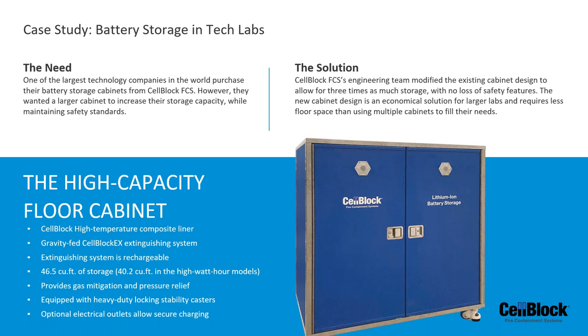Now there is a little downside space-wise associated with doing that. If you increase to the high watt hour shelf, we have to put in more fire suppression mineral, which means if the shelf had 12 inches of clearance, now it may only have 10 inches of clearance or head height of freeboard, because we just have to put more material in. But that's the rundown on the cabinets. Again, they are 100% full containment.